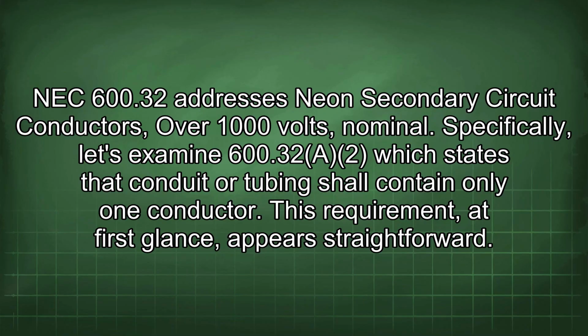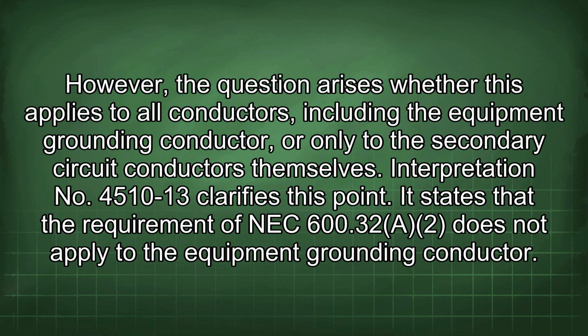NEC 600.32 addresses neon secondary circuit conductors over 1000 volts, nominal. Specifically, let's examine 600.32(A)(2), which states that conduit or tubing shall contain only one conductor. This requirement at first glance appears straightforward. However, the question arises whether this applies to all conductors, including the equipment grounding conductor, or only to the secondary circuit conductors themselves.